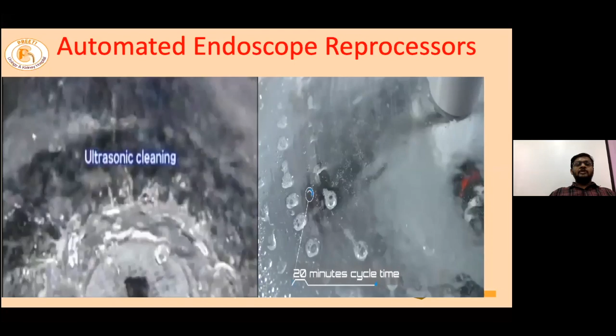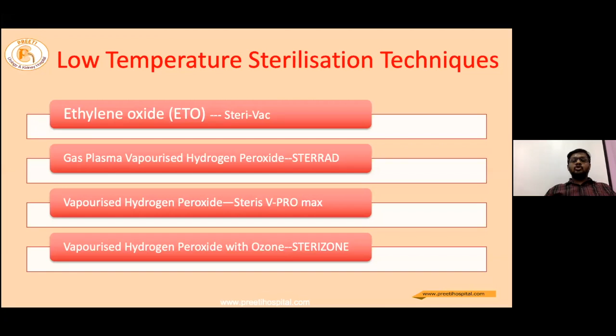And for sterilization, the most common are the low temperature sterilization techniques. There are various types of techniques available. The first and foremost introduced was ethylene oxide, ETO. Then came the gas plasma vaporized hydrogen peroxide sterilization system, mainly called STERRAD. Vaporized hydrogen peroxide system, STERIS V Pro Max. And the latest new kid on the block is vaporized hydrogen peroxide with ozone, manufactured as Sterizone.